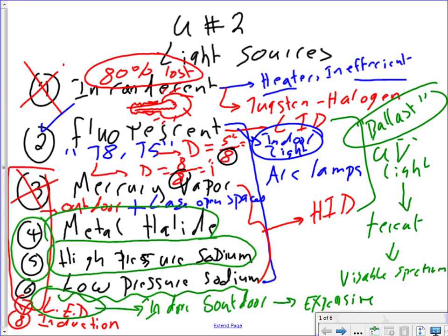The last thing I would like you to look at is page 22. Probably for you beginners in this science, page 22 is the best. It compares the efficiency of all these fixtures that we talked about. On the horizontal side, it says efficiency in lumens per watt. Always lumens per watt: the more lumens per watt, the more efficient the fixture is. Let's start with incandescent lamps, 20 lumens per watt. Mercury vapor, 55. Fluorescent, 100 lumens per watt. Metal halide, 125. High pressure sodium, 140. Low pressure sodium, 200. And the perfect energy conversion, of course, you're not going to have a perfect one, is 683.